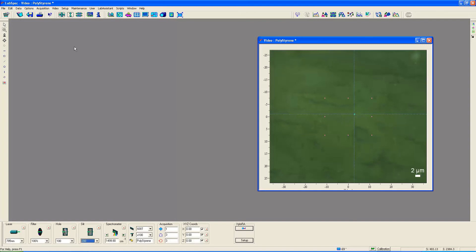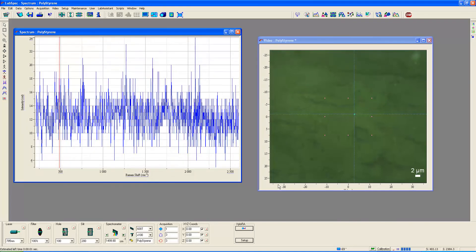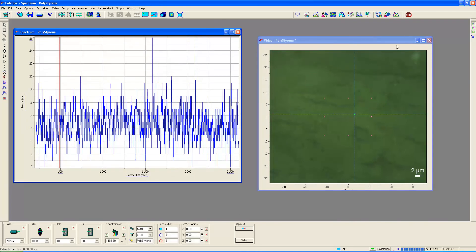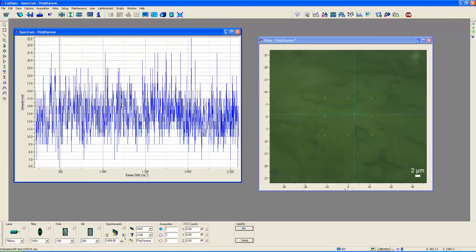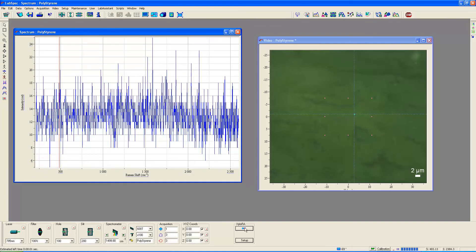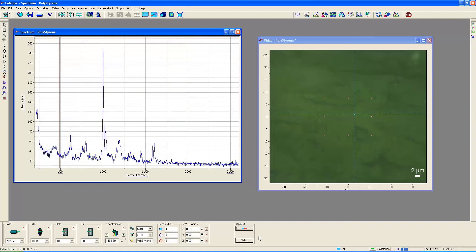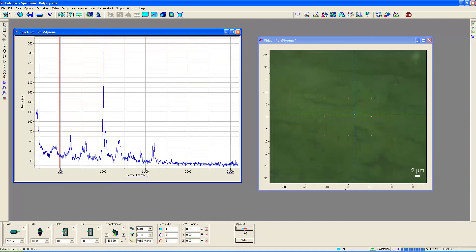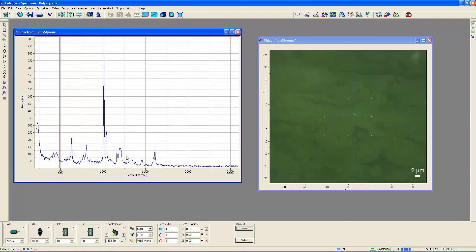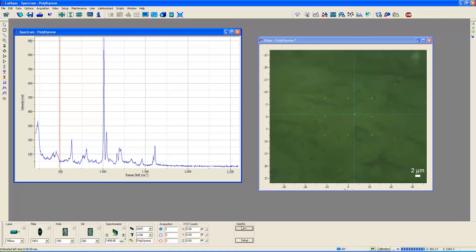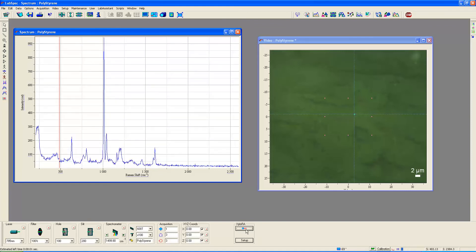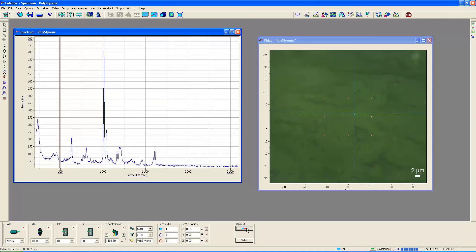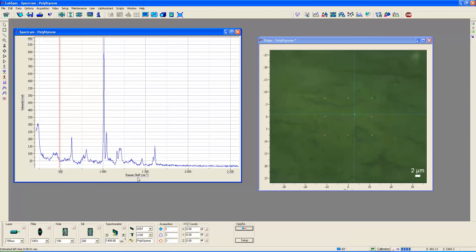Let's take a look at a real-time display with the beam currently focused on the surface. Notice I had been in the video mode, but I had stopped that, and now I go to real-time display, and I don't get a signal. Well, that's because I don't have the laser on. As you see now, if I click on the laser, there's our spectrum. This is a common mistake that people will make. Always check to see that the laser is illuminating the surface.